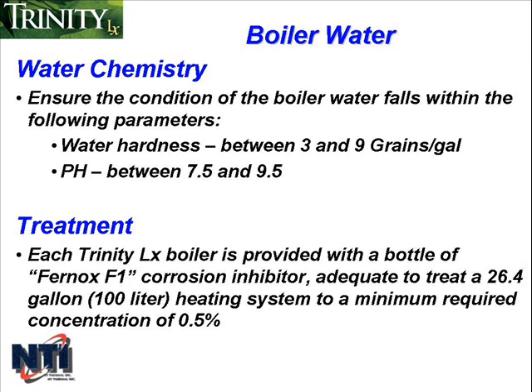Each Trinity Lx boiler is provided with at least one bottle of Fernox F1 corrosion inhibitor. The LX 800 comes with 2 bottles, the rest of the boilers come with 1. A bottle is enough to treat a 26.4 gallon or 100 liter heating system to a minimum required concentration of 0.5%. Systems with greater volume will require more inhibitor. For more information on performing the treatment, follow the instructions with the Fernox F1 protector.